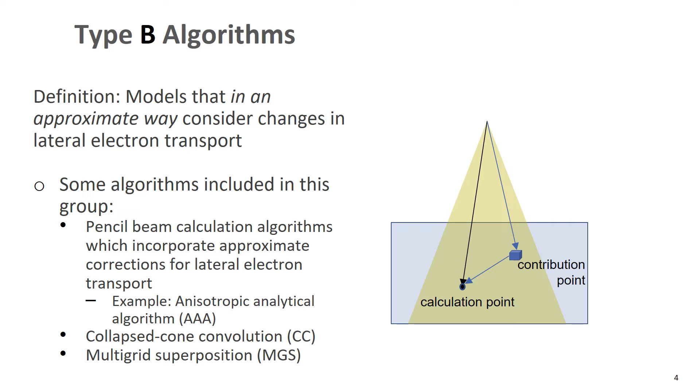Type B algorithms are models that in an approximate way consider changes in electron transport. So some algorithms that fit into this group are pencil beam calculation algorithms, which incorporate approximate corrections for lateral electron transport. One example would be the anisotropic analytical algorithm. Also collapsed cone convolution and multi-grid superposition.